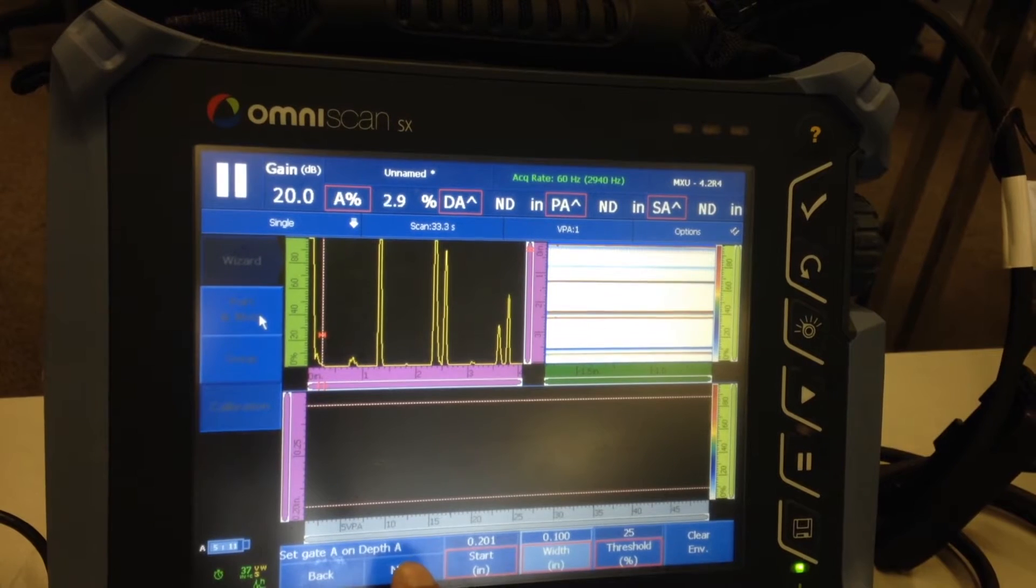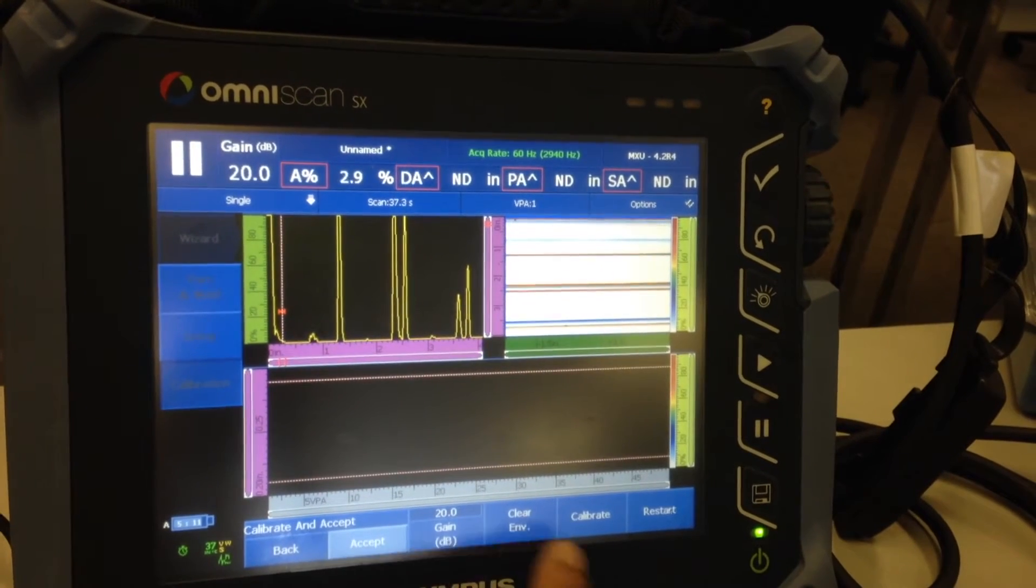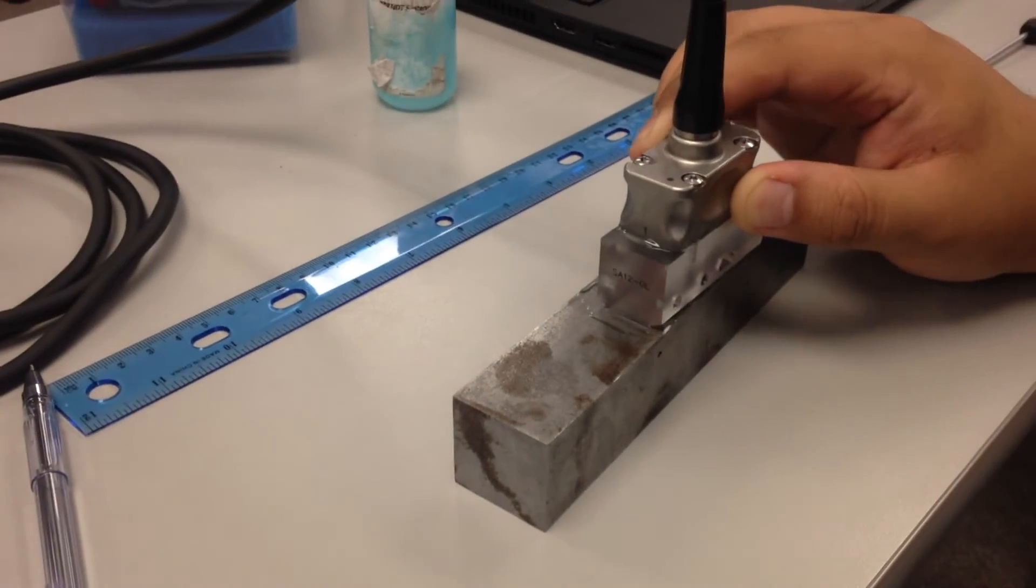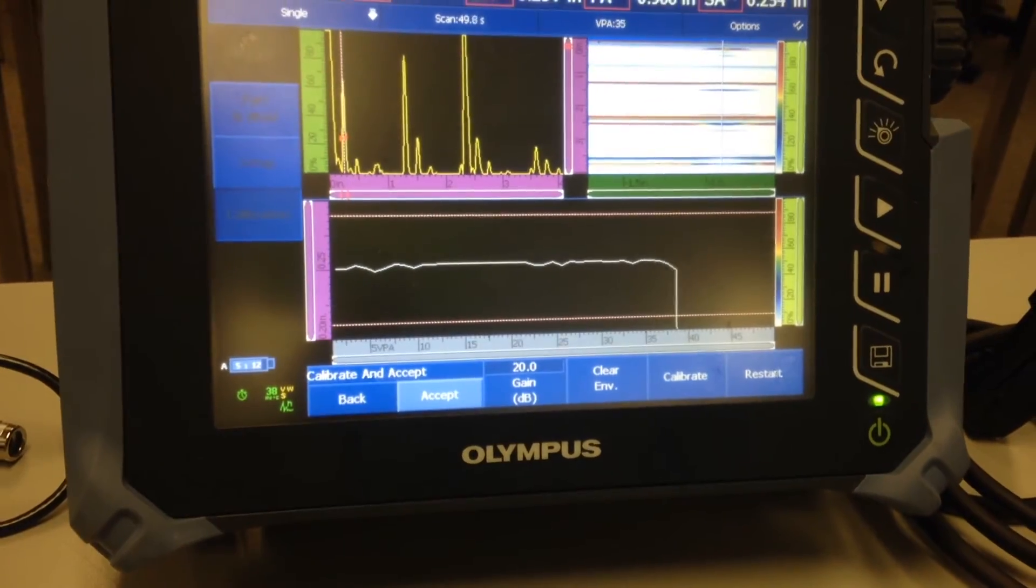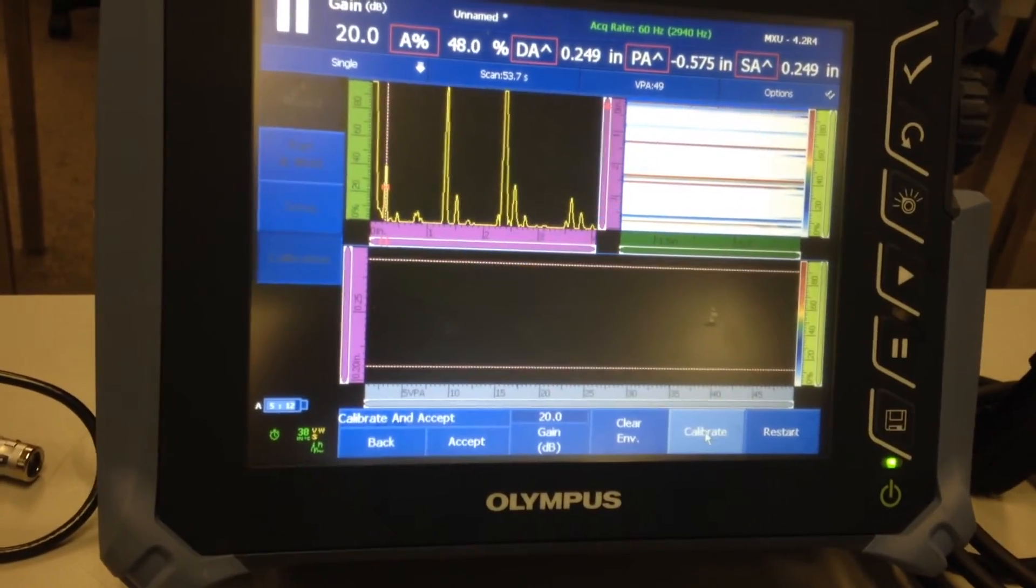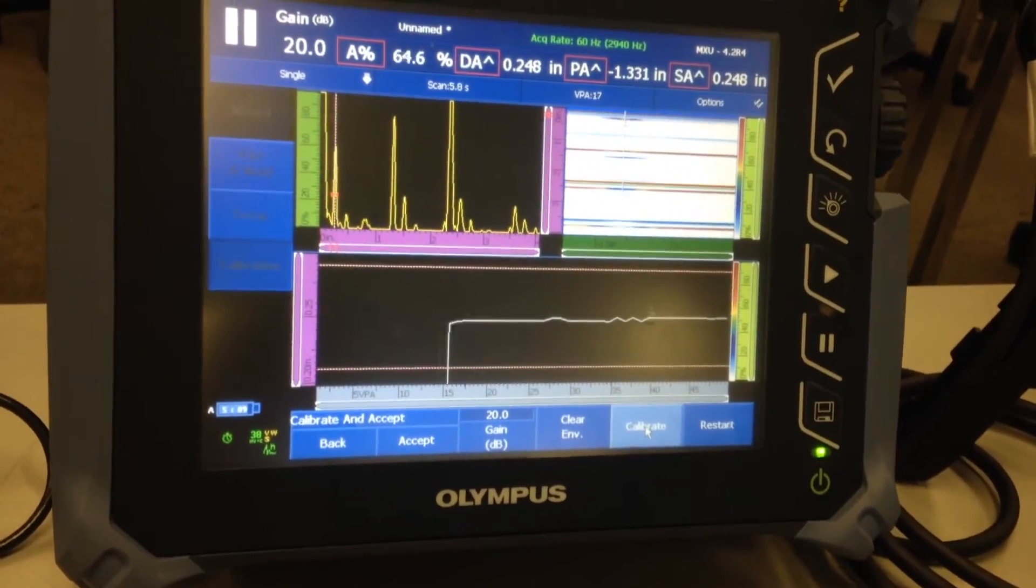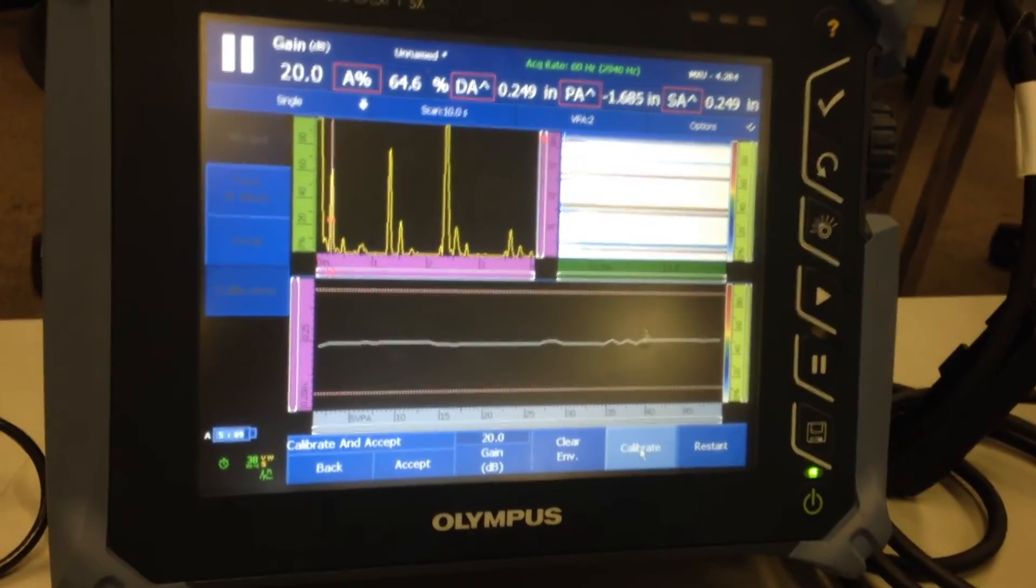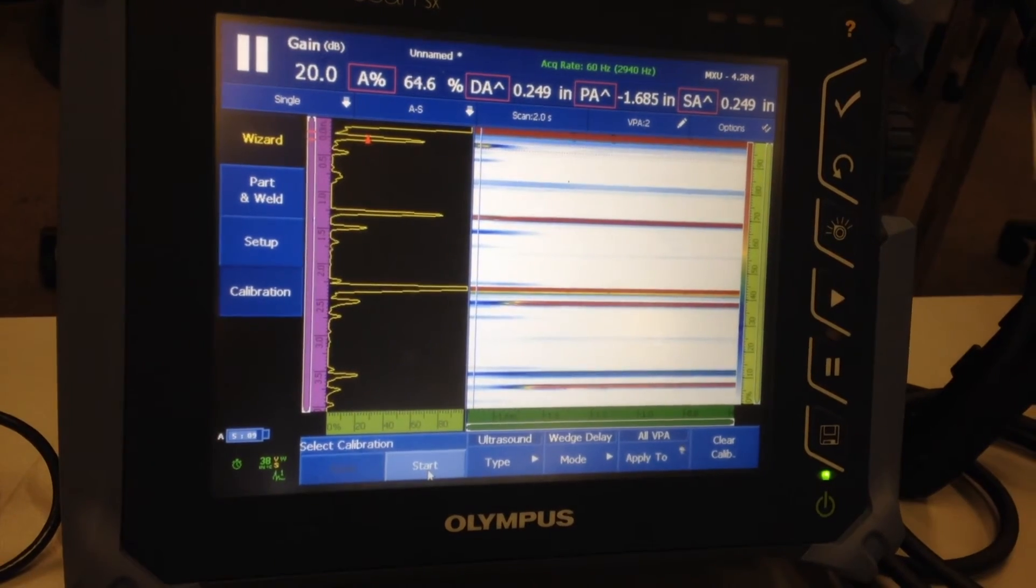So I'm going to start my gate a little before quarter inch and width, which will take it to a little bit after quarter inch, so 0.1. Now my gate is from 0.2 to 0.3. Click next. Once I see my calibrate screen, I'm ready to put some couplant on the calibration block and get a signal from the quarter-inch side drill hole. Once I get that, click calibrate and get a signal again. Once I get a nice straight line, I hit accept. I'm done with my wedge delay calibration.